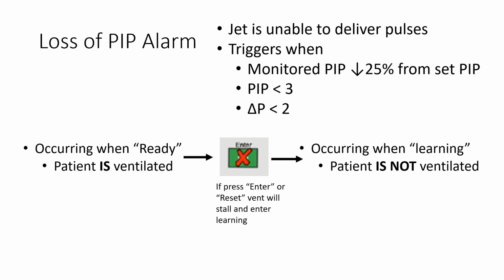The loss of PIP alarm is activated when the jet ventilator is unable to deliver or monitor jet pulses. This alarm will activate when the monitored PIP has fallen 25% below the set PIP, the monitored PIP is less than 3, or the monitored value for delta P is less than 2.